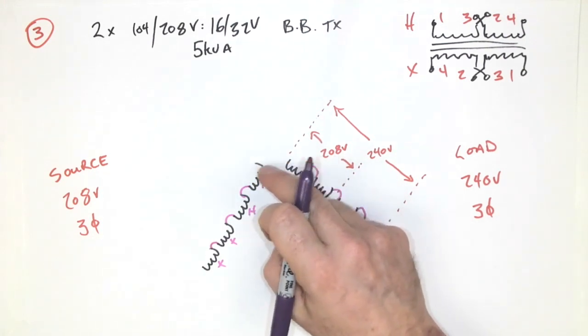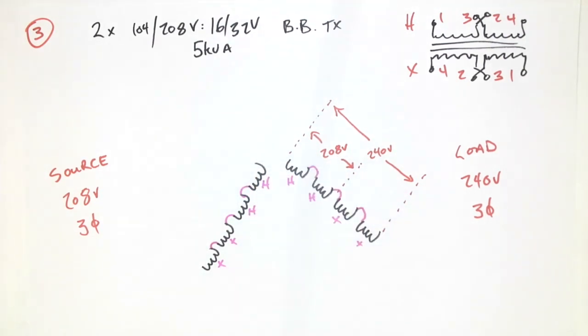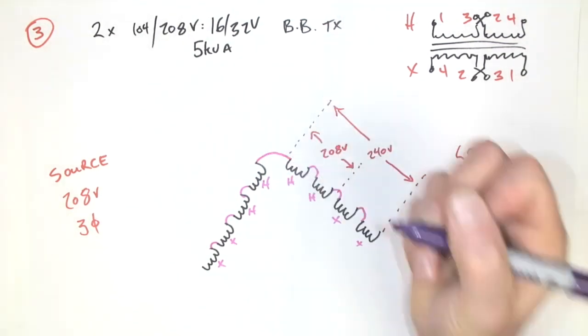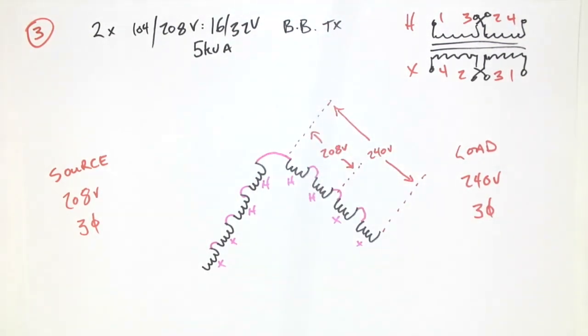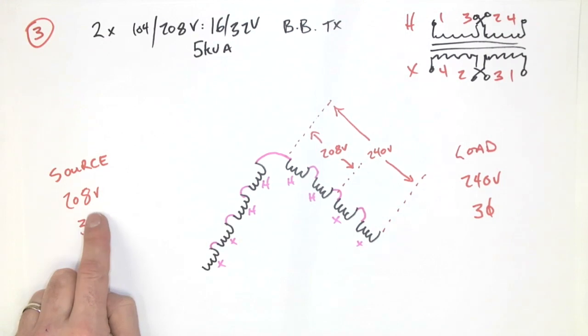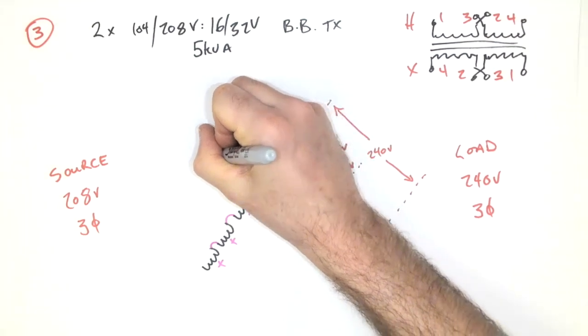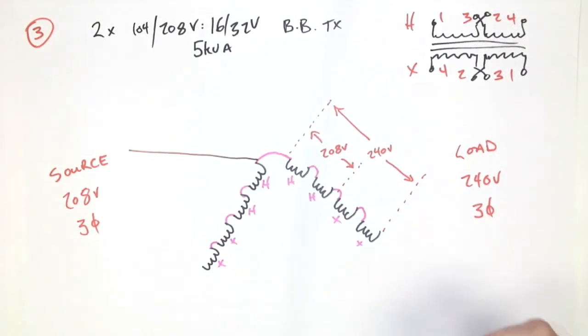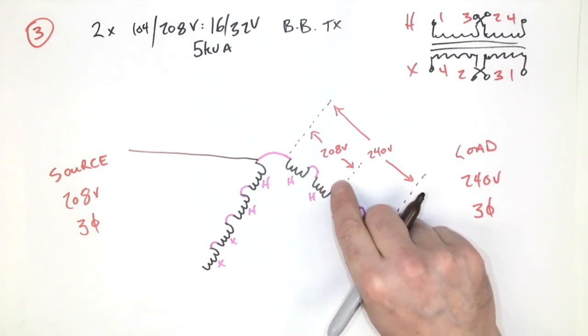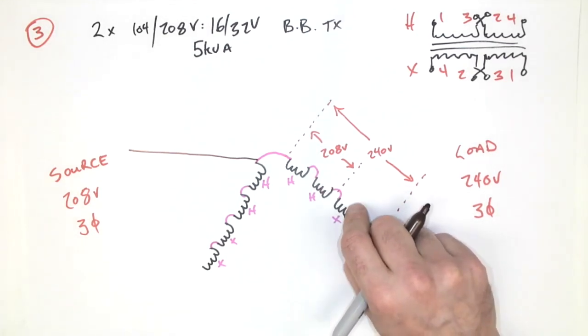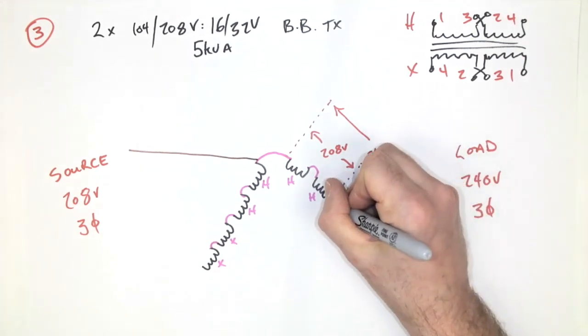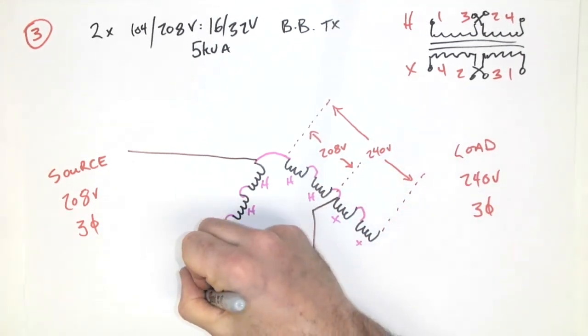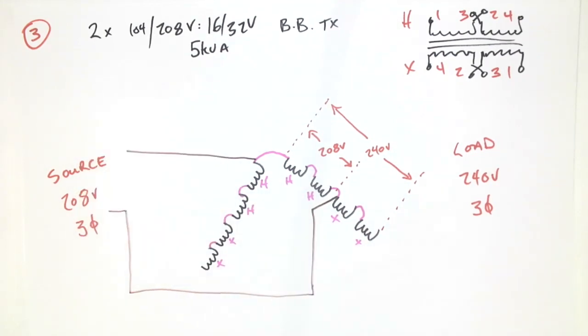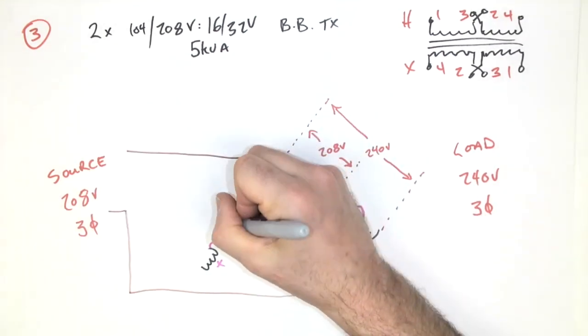So we know that this must connect together because this is the open delta connection point, the star point, or not star point, but the common point. The next step, we're going to connect our source to the 208 volt connection points. The first one is going to go here. The second one, I'm going to take from this center connection point between the H and the X, and it doesn't matter which terminal I take it from, right? So I'm just going to choose to take it from this one here. And finally, from the third leg right here.